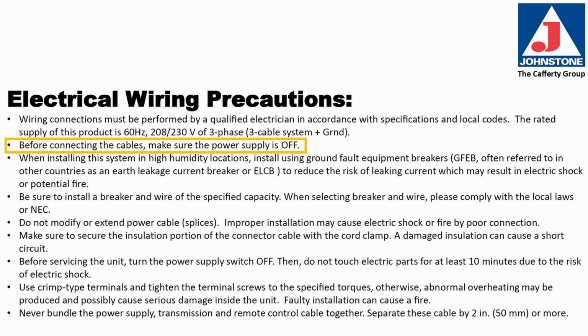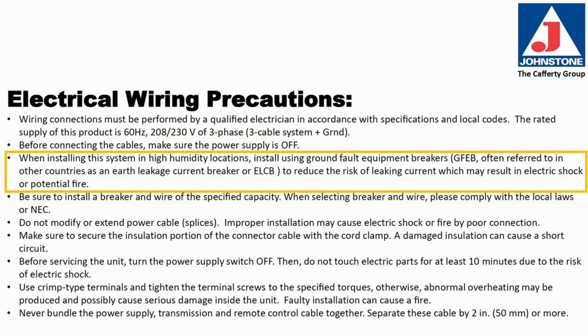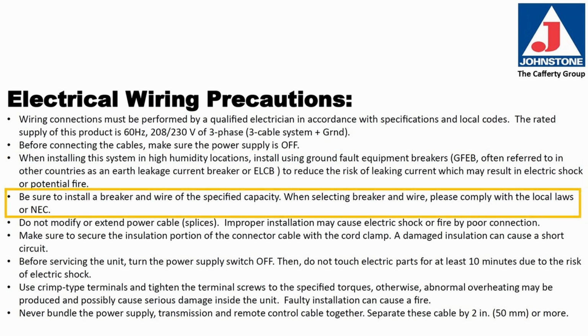Before connecting cables, make sure that the power supply is turned off. When installing the system in a high humidity location, use a ground fault equipment breaker, or GFEB, to reduce the risk of leaking current, which may result in electrical shock or potential fire. Be sure to install the correct size breaker and wiring. When selecting breaker and wire size, please comply with your local codes and the National Electric Code.